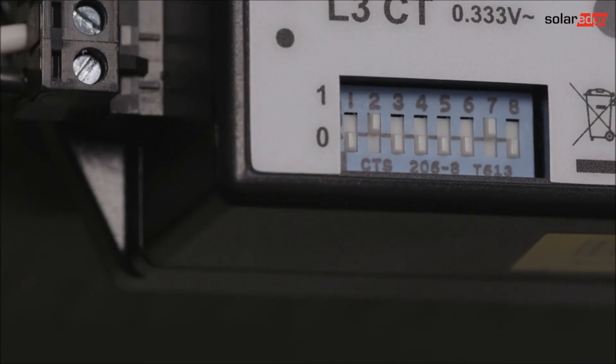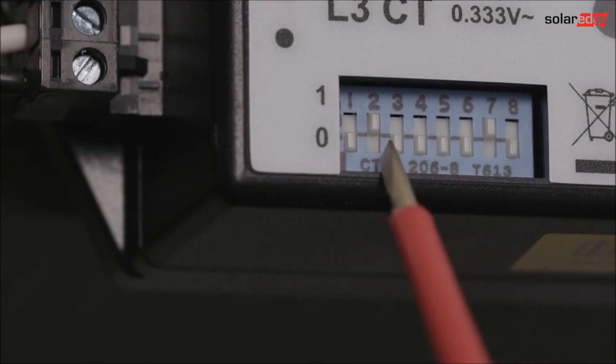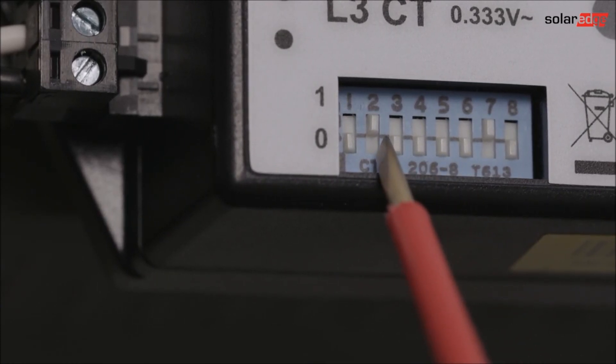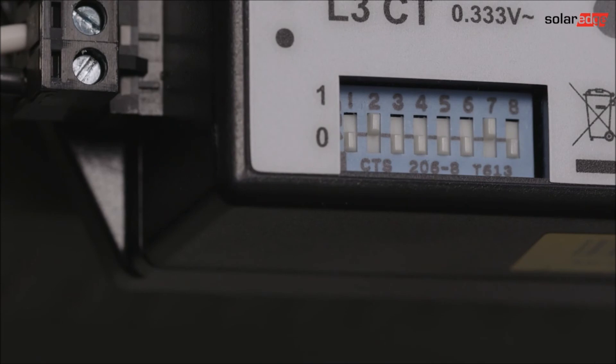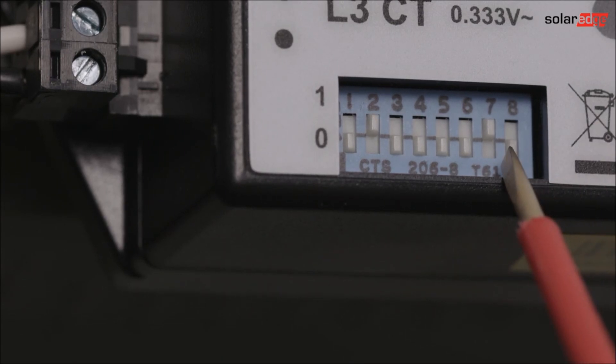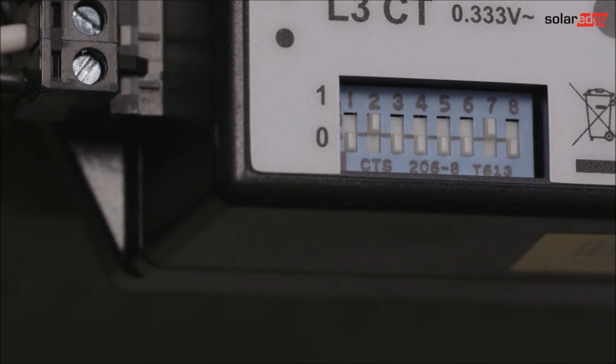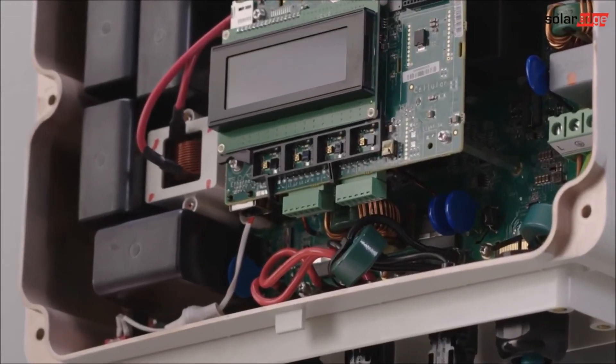Now we need to configure the meter. DIP switch number two needs to be up which is the on position to assign device ID 2. If a meter with a WND part number is the first or last device on the RS485 bus move DIP switch 7 up to terminate the bus. Otherwise use the inverter termination.